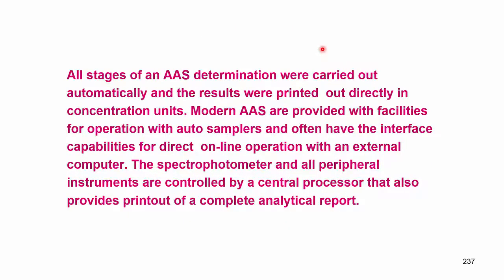So, all stages of atomic absorption determinations are carried out automatically, and the results are printed out directly in concentration units. Modern AAS are provided with facilities for operation with auto samplers and often have interface capabilities for direct online operation with an external computer also.